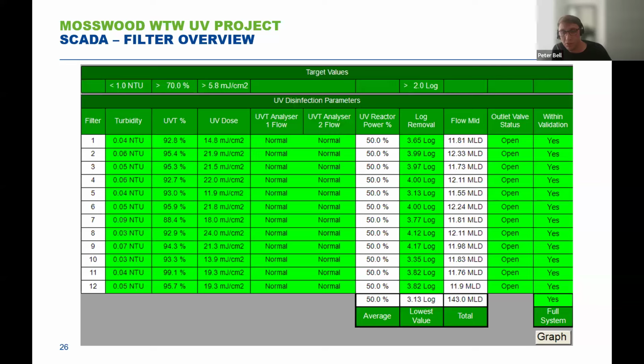Now, the approach we went with was to simplify our operational understanding and how we reacted to it. If one filter fell out of validation, then the whole system would fail, and we were unable to accurately see where that potential cryptosporidium had come from. So we basically based it on the whole system must be in validation to prove its worthiness across the plant. Let me give you a little bit of indication of some of the operational parameters that might be useful as well.